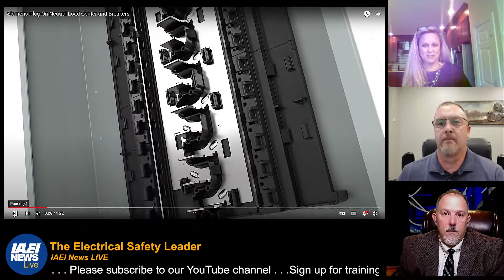One thing all the manufacturers have done is move to the plug-on neutral. You were talking earlier about all the grounds, neutrals, and load wires coming in, and now you have all these pigtails added onto the load center. You've probably seen someone open a panel and it looks like a rat's nest going down the gutters on either side of the breakers, with all the wires we've added for AFCI and GFCI technology, because you've got to have power to the brains of the breaker. That pigtail, that neutral wire, provides the power for the brains. Now we have plug-on neutral load centers that all of us carry.